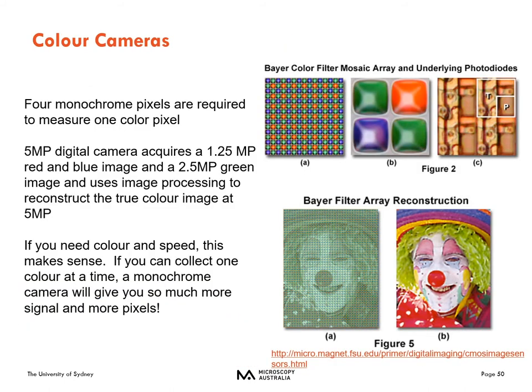In fluorescence microscopy, we typically use a monochrome camera since we know the color from our filter cube and can false-color images later in software. For brightfield imaging such as H&E or DAB, you may want a color camera. Color cameras use a Bayer filter in front of four monochrome pixels — two green, one red, one blue — to determine the color value in the image.